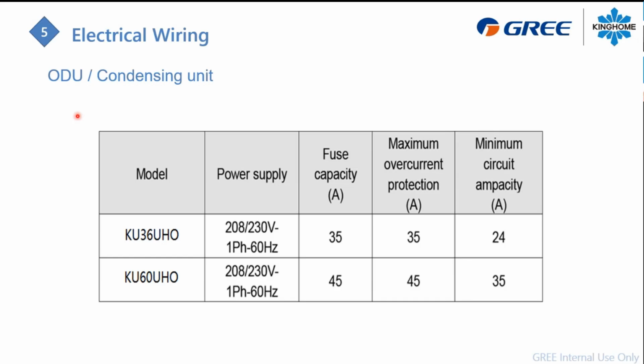So for the outdoor unit, the power will be, again, L1 and L2. Maximum fuse for a 2 and 3 ton system will be 35 amps. So a 30 amp breaker with a 10 gauge wire is good enough to make your installation. And for a 4-5 ton unit, the maximum is 45. So you will use here a 40 amp breaker with the number 8 wire gauge, that's big enough to make your connection here.